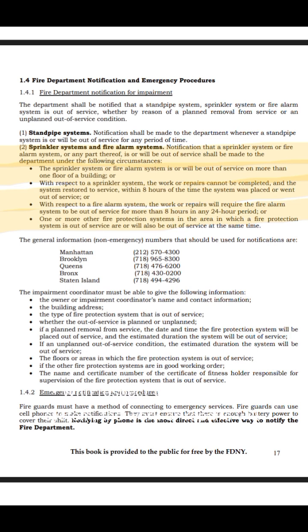with respect to a fire alarm system, the work or repairs will require the fire alarm system to be out of service for more than 8 hours in any 24-hour period, or one or more other fire protection systems in the area in which a fire protection system is out of service are or will also be out of service at the same time. The general information non-emergency numbers that should be used for notifications are listed below.